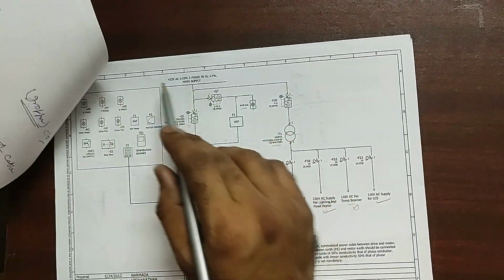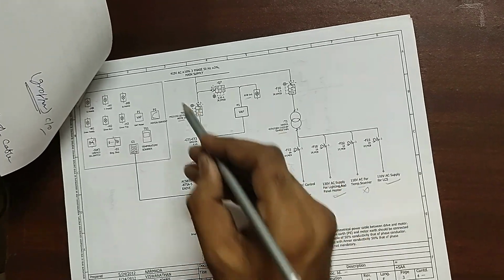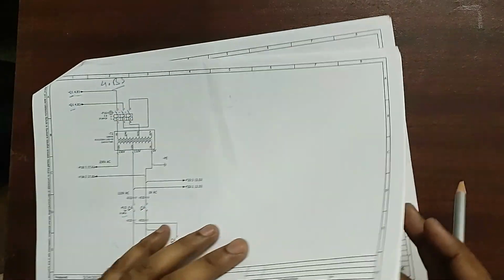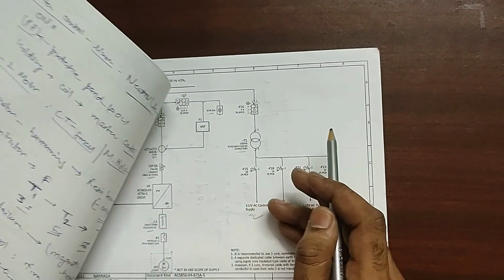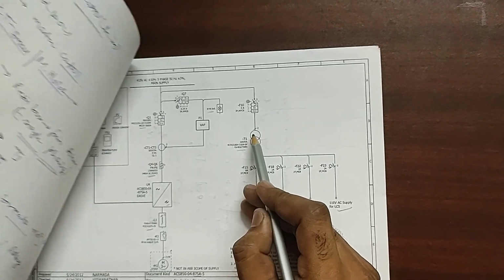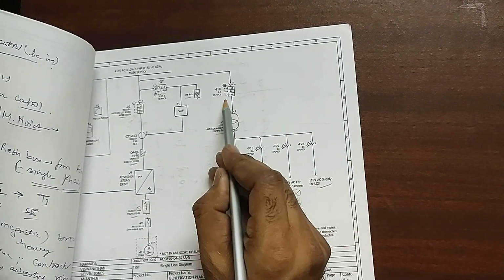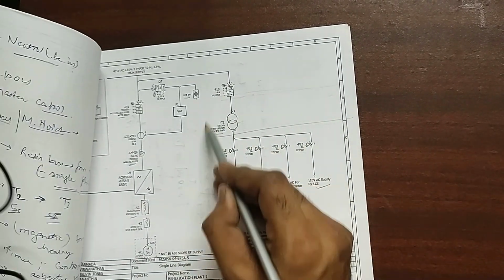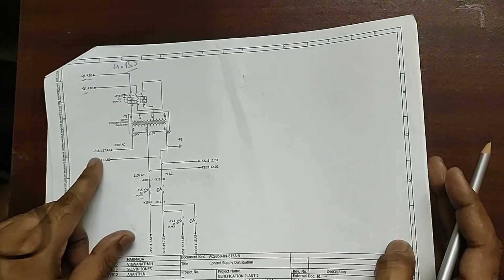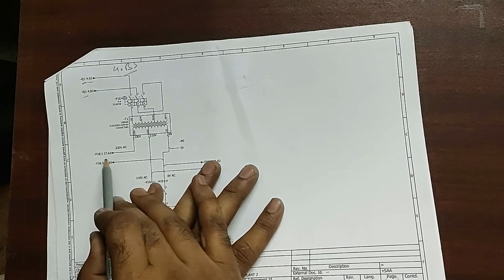From there we are taking 2 tappings for the control transformer. B and 3. This part. Okay. Not that part. Now it is B and 3. I think there is some mistake because here they are taking the transformer supply. Okay. B and 3. This is the control transformer. It has to be B6. This one. And from the control transformer we are getting the 230 volt supply here.